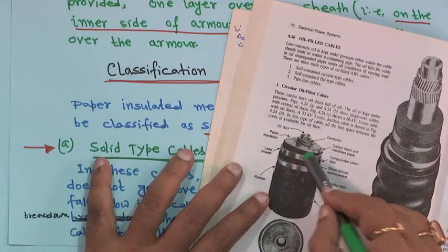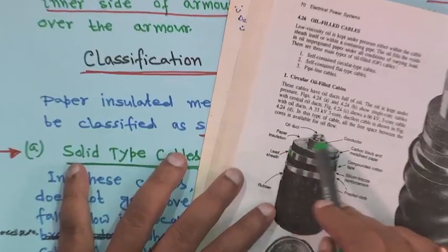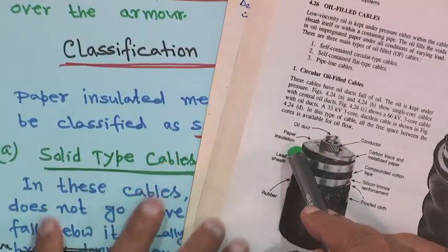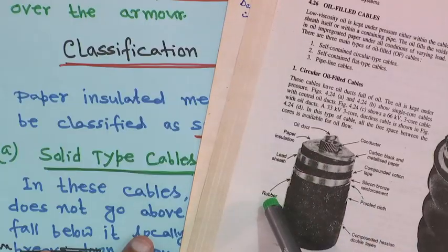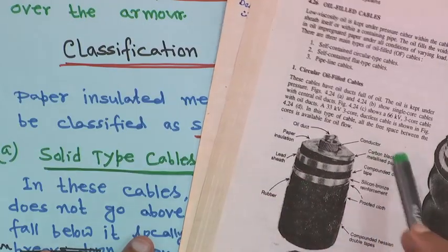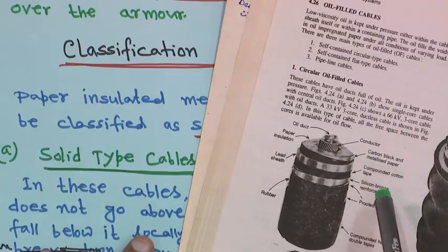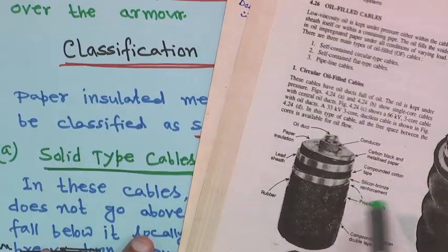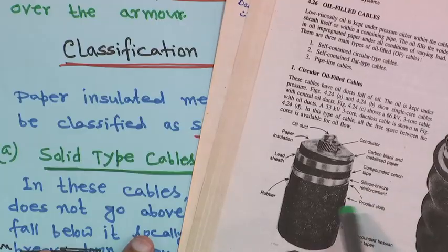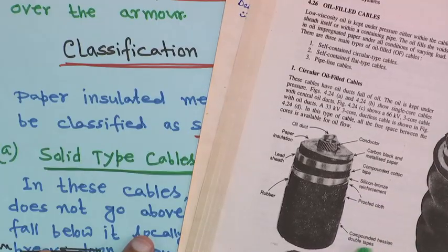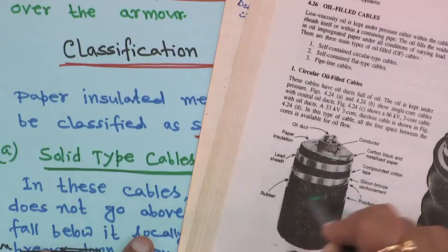Of course, this is an oil duct cable, that does not matter, forget about that. Look, after this the paper insulation is there, over the insulation the lead sheath is there, and after that the rubber is also there, and this is the conductor. Here carbon black and metallized paper is also there, then compounded cotton tape, then silicon bronze reinforcement, and finally proofed cloth and compounded Hessian double tapes, right. Look, so many materials are there for the cable.